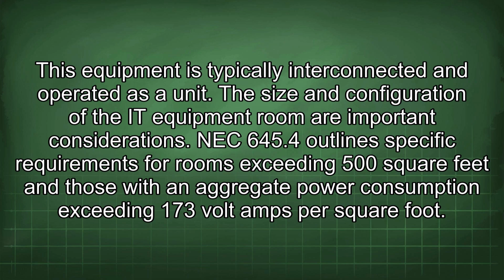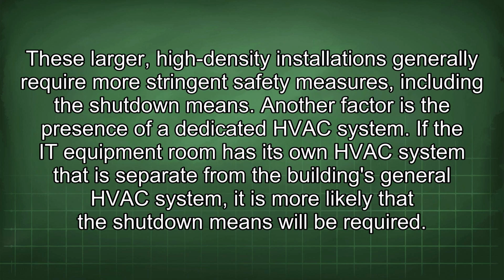NEC 645.4 outlines specific requirements for rooms exceeding 500 square feet and those with an aggregate power consumption exceeding 173 volt-amps per square foot. These larger, high-density installations generally require more stringent safety measures, including the shutdown means.